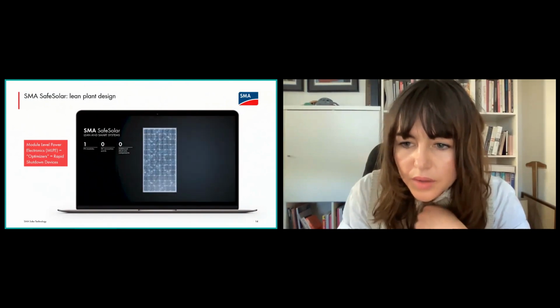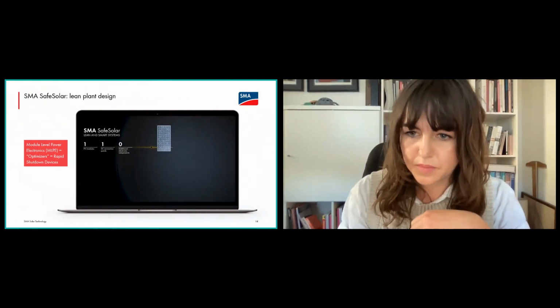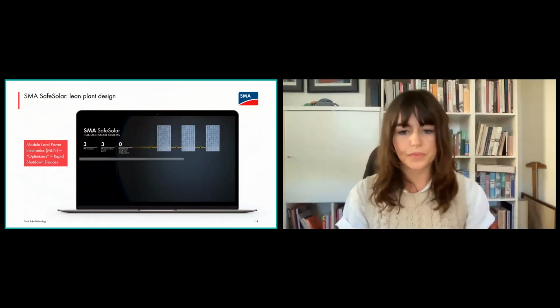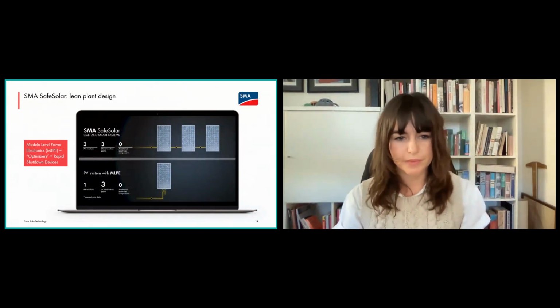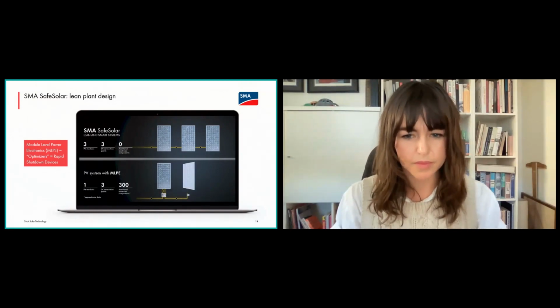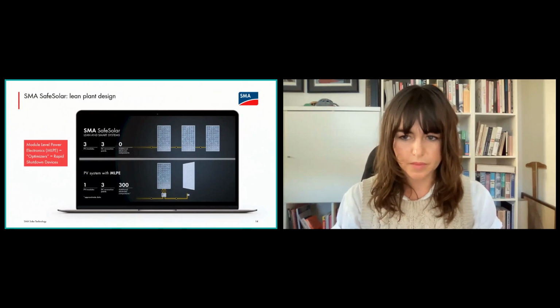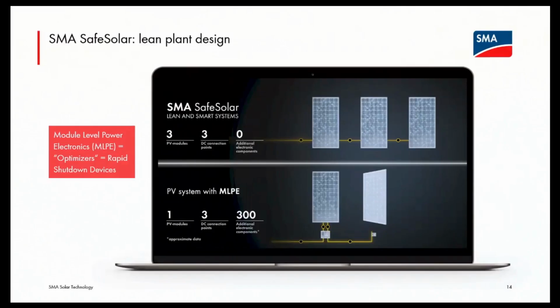For a system with string inverters, you've got one interconnection point between each module. Each module basically connects with one interconnection point to the module next to it. In a system with MLPE, you're adding the optimizer or rapid shutdown device to the PV module, so you have two interconnection points at the bottom, connecting the optimizer to the PV module. Then you have to interconnect that to the second module next to it. So you've got 3 points of interconnection per module instead of 1. I hope this answers the question.